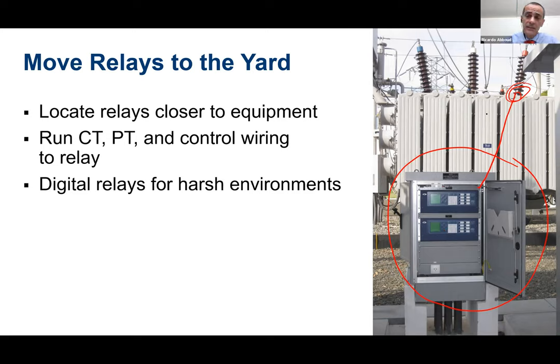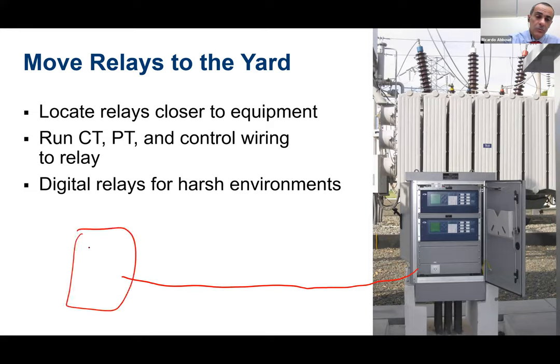So I'm going to connect the CTs and VTs and all of the digital inputs and outputs with those short copper cables. Of course, for this approach, we need to have digital devices that can be installed in the yard. That means they must be designed for harsh environments. I'm talking about temperatures. I'm talking about electromagnetic interference. So we need to have some rugged devices to be installed in the yard. Okay? This is a really good approach. And now I'm going to run fiber cables from that cabinet to the control room where I have the HMI, and also where I have the gateway that will be connected to the remote control center. So instead of running copper cables from the switch yard to the control room, I'm running just fiber optics.